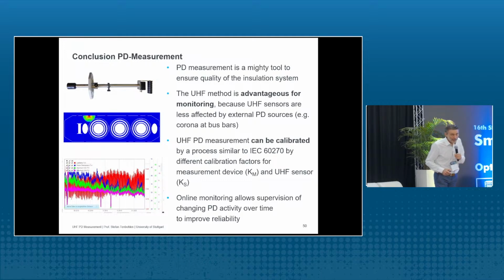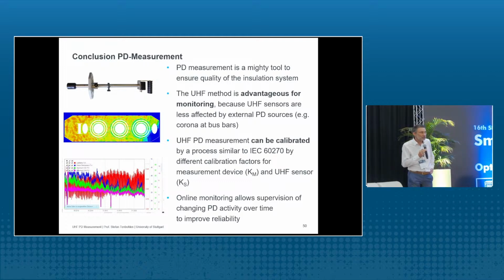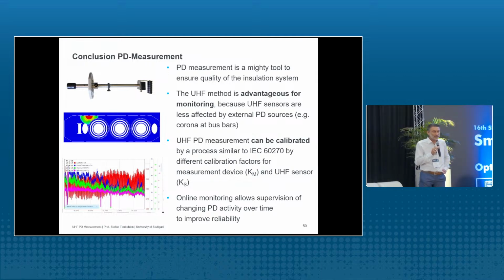So, a long time. Now we come to the conclusion, because it's almost lunchtime. I explained to you that PD is a mighty tool to ensure the quality of the insulation system. And if you apply this technique online, then UHF PD measurement has advantages, because it's quite immune to noise compared to electrical PD measurement. And online monitoring is possible in order to really monitor the PD behavior dependent on different operational conditions of the transformer.